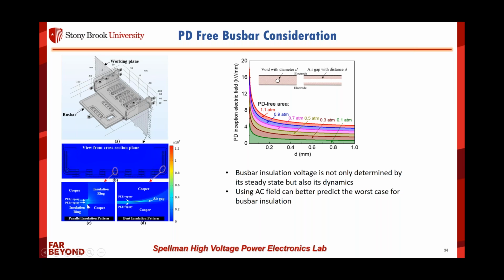In this way, we have a lot of non-uniform distribution of the electric field. In our insulation design, we encountered these kinds of challenges, and we developed our own PD-free area at different air pressures. With that, we provided this information to our bus bar manufacturer and asked them to enhance where they should improve the insulation film and where they should put more epoxy. We got our bus bar back, and everything works well according to our testing.